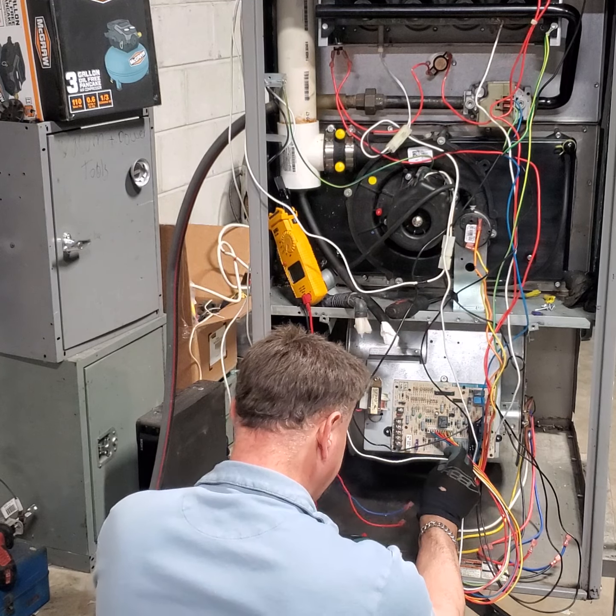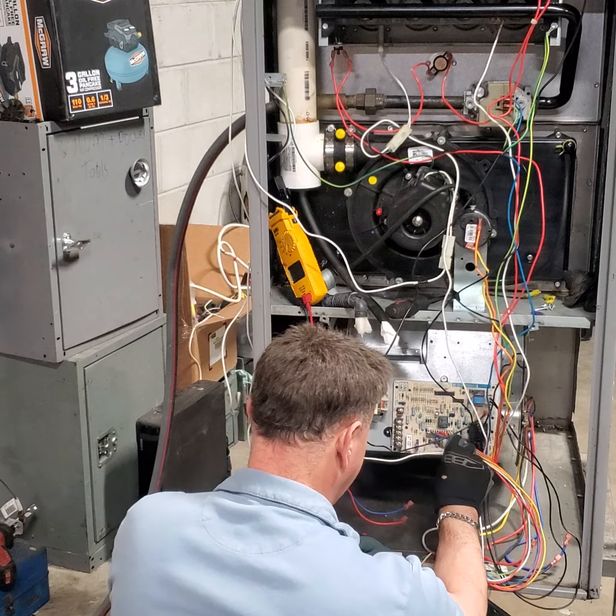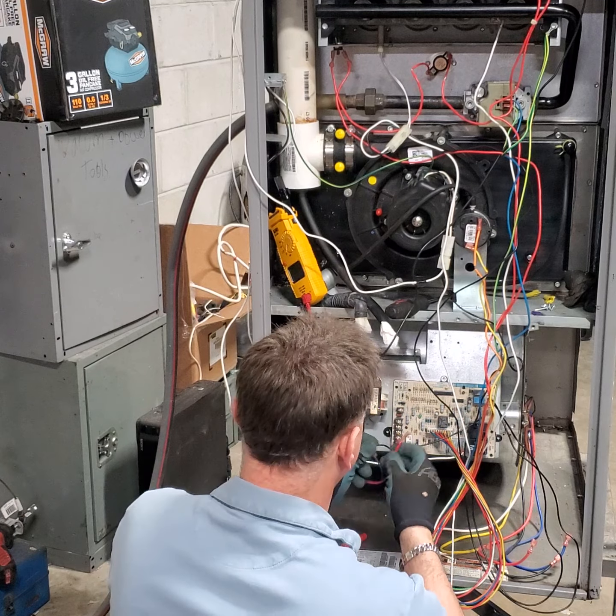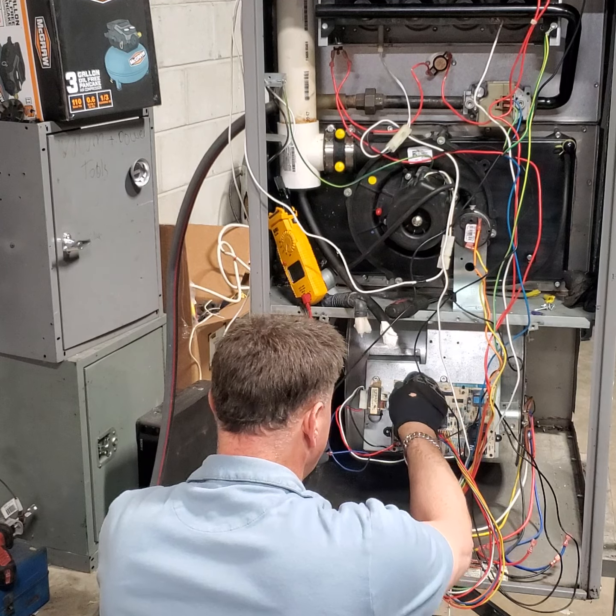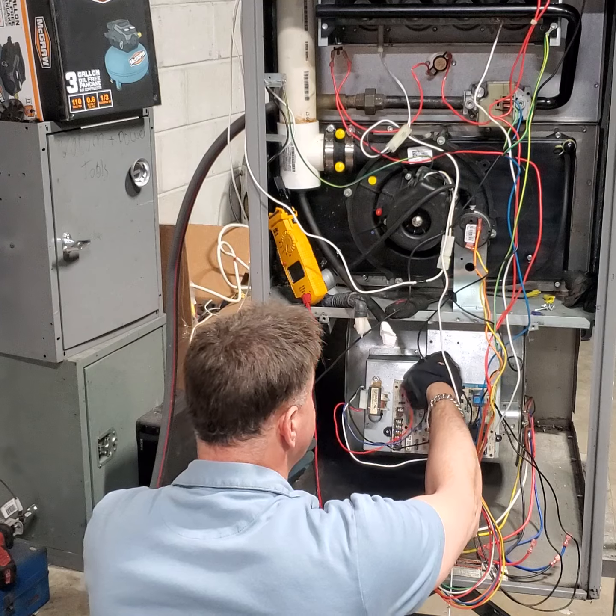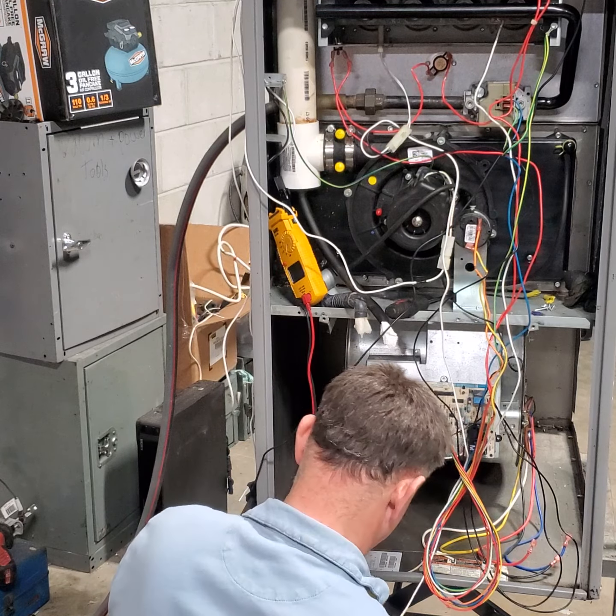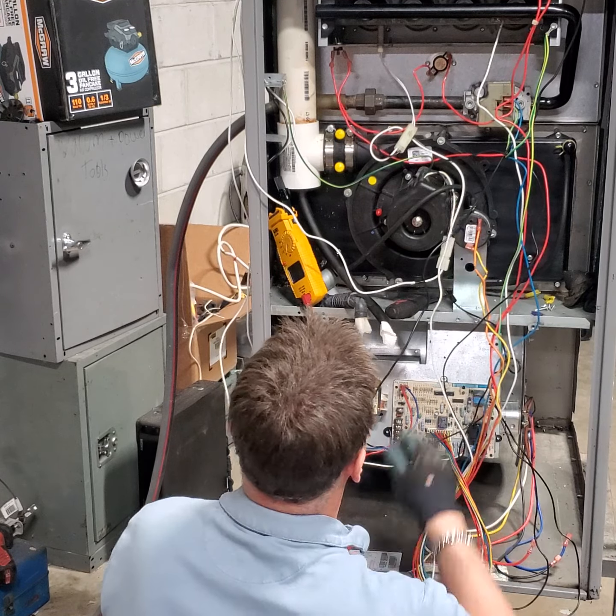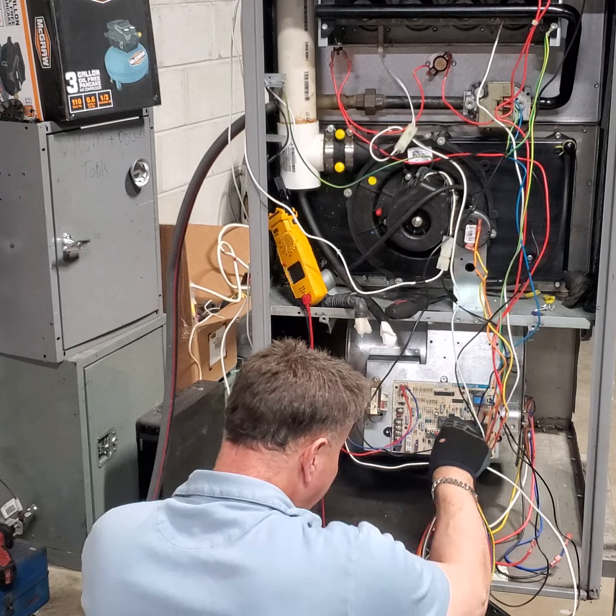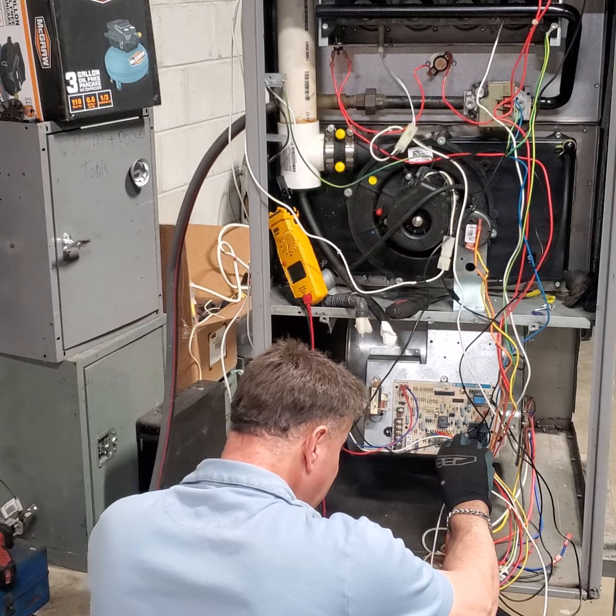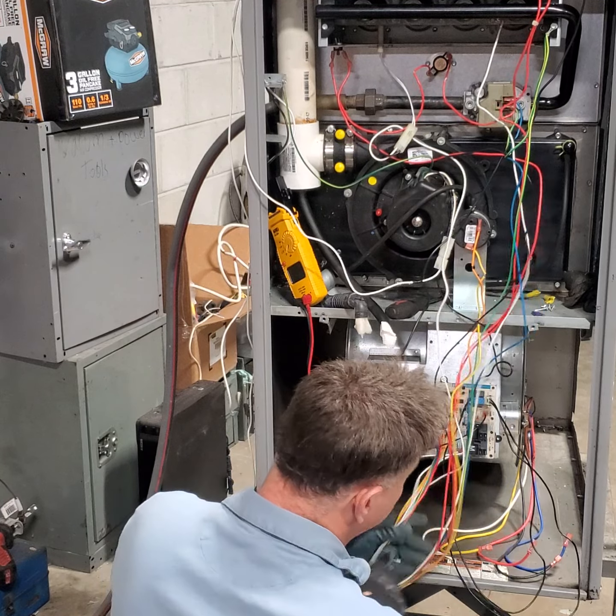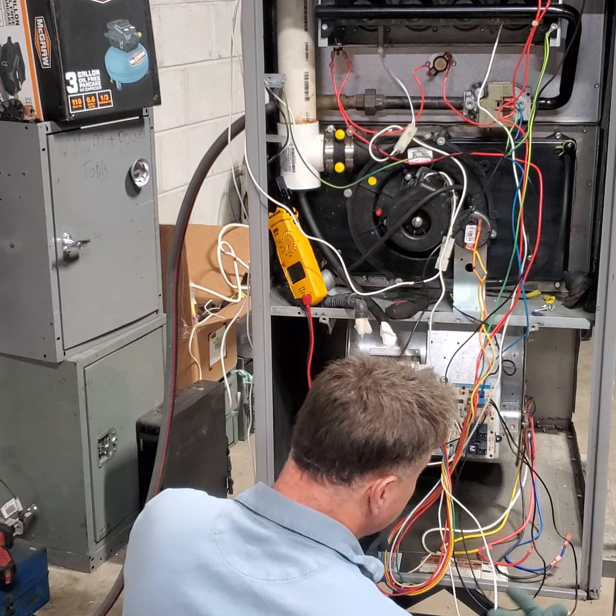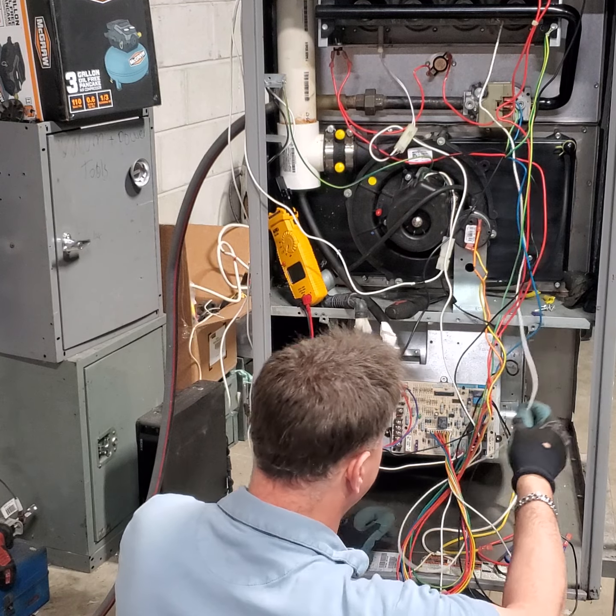Common goes anywhere—you can put it here. Then this same thing, you follow red for the 24 volt circuit. And then this wire here goes from the igniter, again anywhere in the common section or in neutrals. So all the white wires usually go to neutral. It doesn't matter where—some other furnaces show you exactly where they should go, but not all of them.